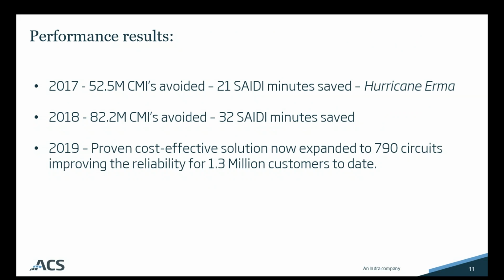So some notable results. In 2017, over 52 million CMIs were avoided, contributing to 21 SAIDI minutes. And this was during Hurricane Irma. The next year, 2018, for the total year, it's 82 million CMIs, contributing 32 SAIDI minutes. The system continues to expand as an extremely cost-effective solution and now serves 790 circuits, improving the reliability for 1.3 million customers to date.